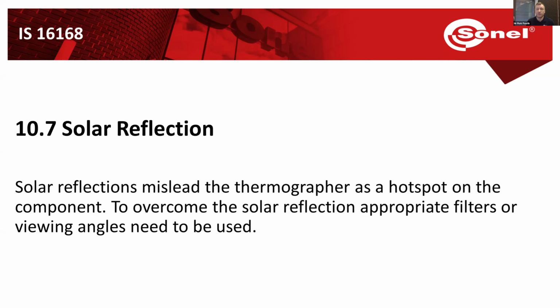Also, let's remember not to point our camera directly at the sun, because the camera has sensitive detectors, and there's so much infrared energy coming from the sun that it can damage the camera. Then you'd have to send it in for repairs to have it adjusted and calibrated.